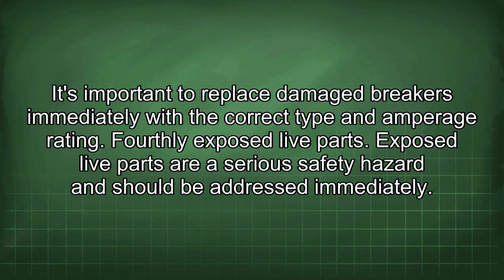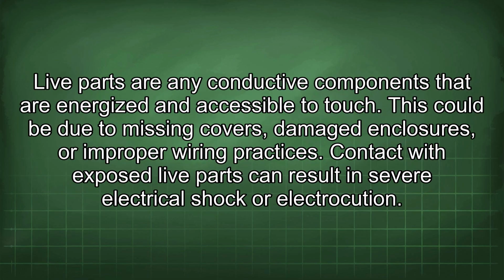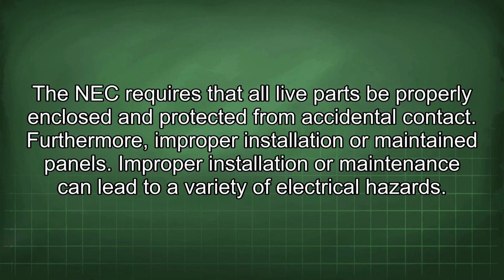Fourthly, exposed live parts. Exposed live parts are a serious safety hazard and should be addressed immediately. Live parts are any conductive components that are energized and accessible to touch. This could be due to missing covers, damaged enclosures, or improper wiring practices. Contact with exposed live parts can result in severe electrical shock or electrocution. The NEC requires that all live parts be properly enclosed and protected from accidental contact.